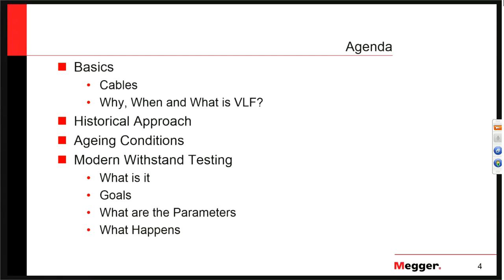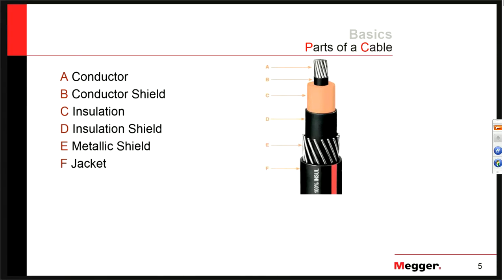As a review, just so we're all on the same page, we'll talk briefly about the parts of a cable. We start with the conductor, the current-carrying component — typically aluminum or copper, and may be stranded or solid. Following that is a thin layer of semi-conductive material. This is often overlooked, but it serves a very important role. In stranded cables, we have peaks and valleys in the outer radius of the cable that can create very severe voltage gradients.